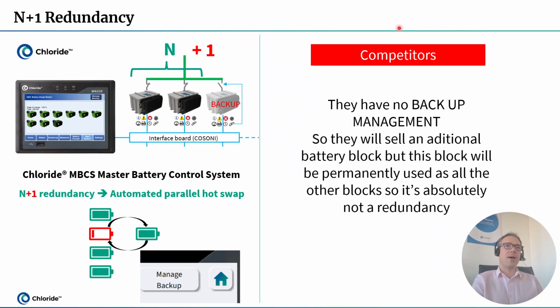The first point I mentioned before is the N+1 redundancy. What we generally see with our competitors is no backup management, I mean managed by the HMI. They will sell an additional battery block like this one, but this block will be permanently used like all the other blocks, so it's absolutely not redundancy. Pay attention to that.